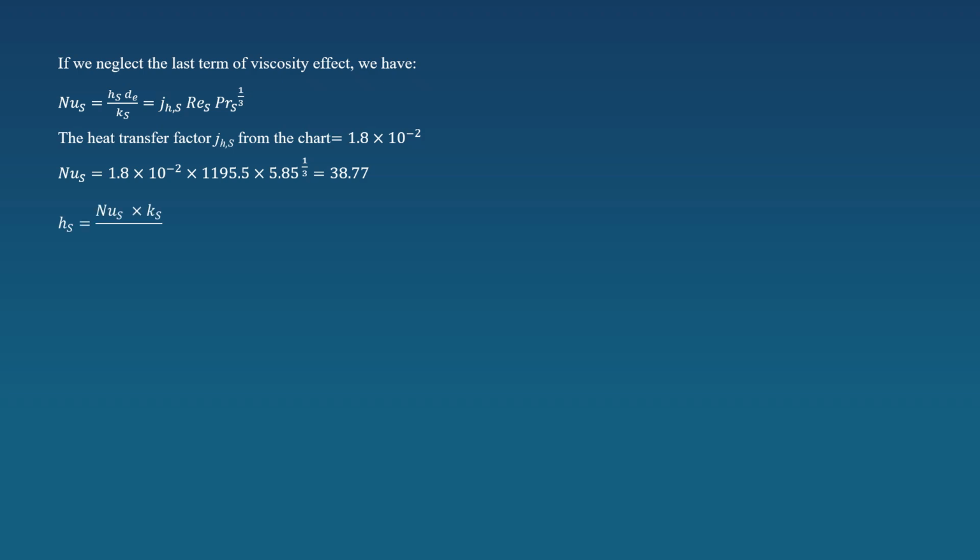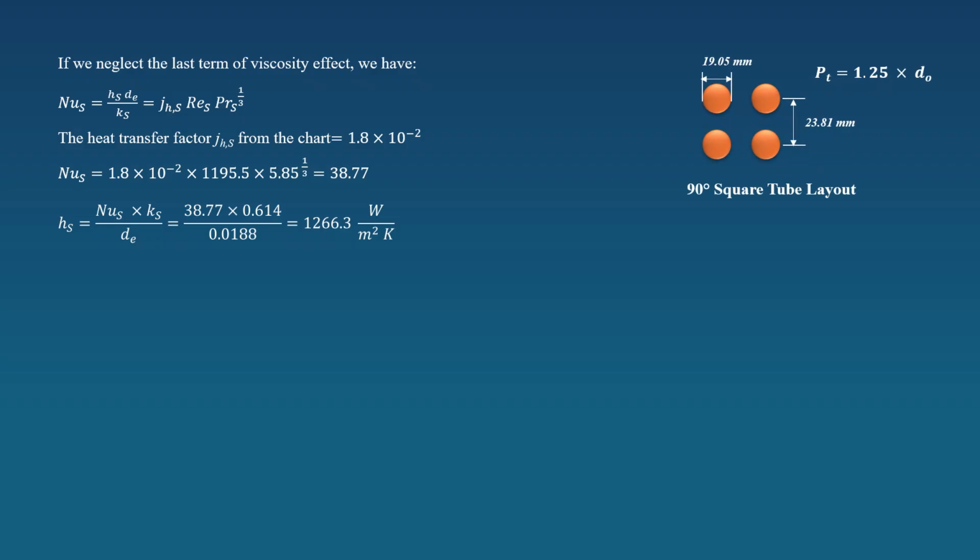With the help of thermal conductivity on the shell side of the fluid and the equivalent diameter, we will get the final value of heat transfer coefficient to be 1266.3 watt per meter square Kelvin.